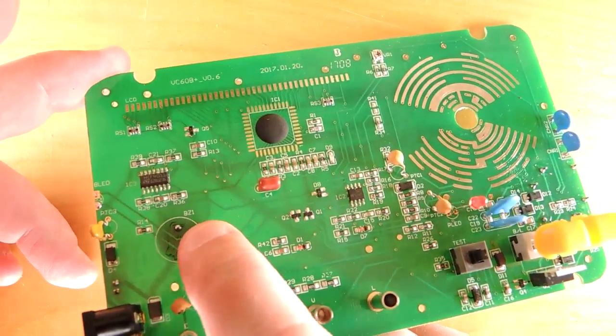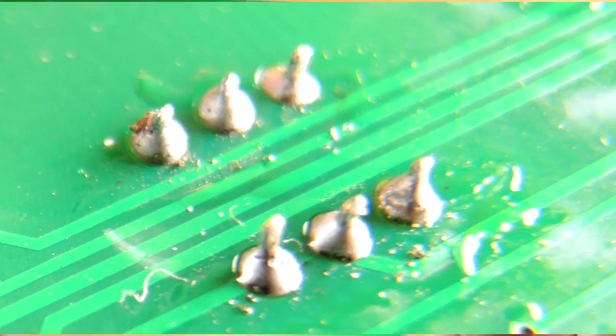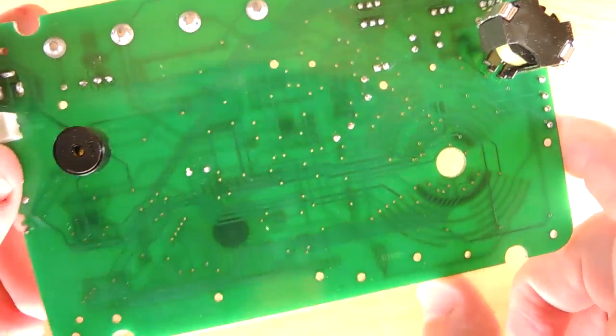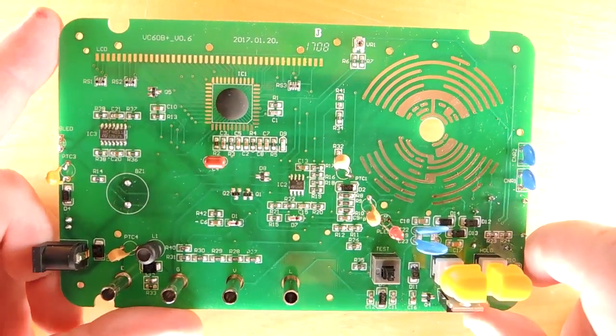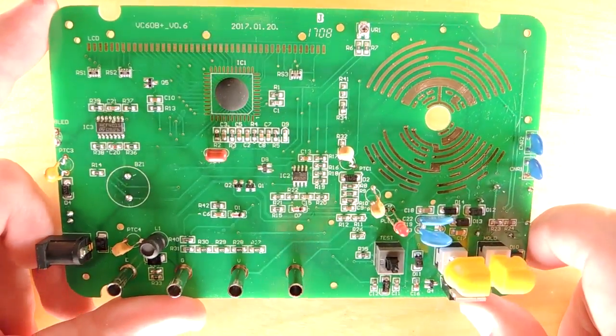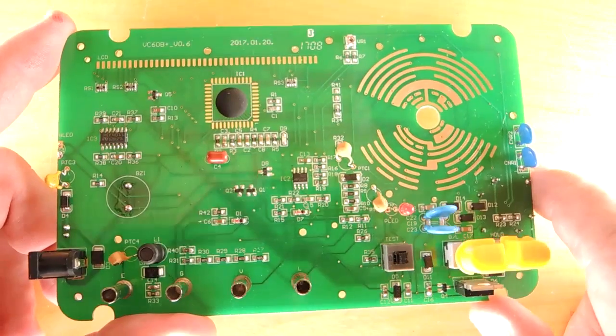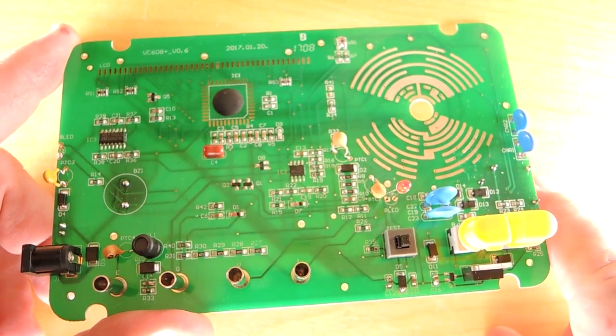Other things, lots of flux residue left over in the assembly. They had some through-hole components. They hand-soldered them on, and they didn't bother cleaning the flux off. Really typical of a meter at the bottom end of the market. And this certainly was the least expensive megohmmeter I could find on Amazon. So, very consistent with other past practices.